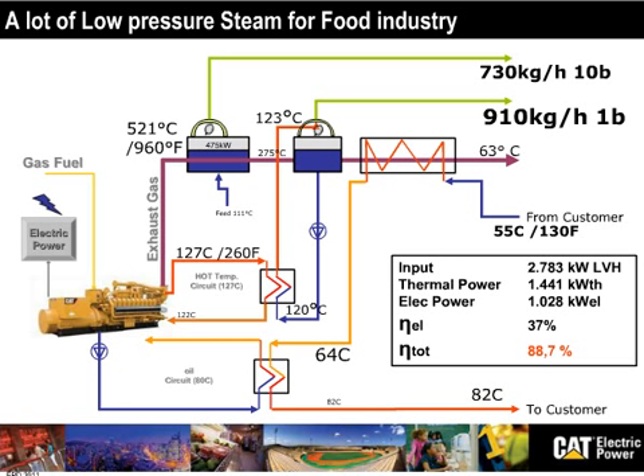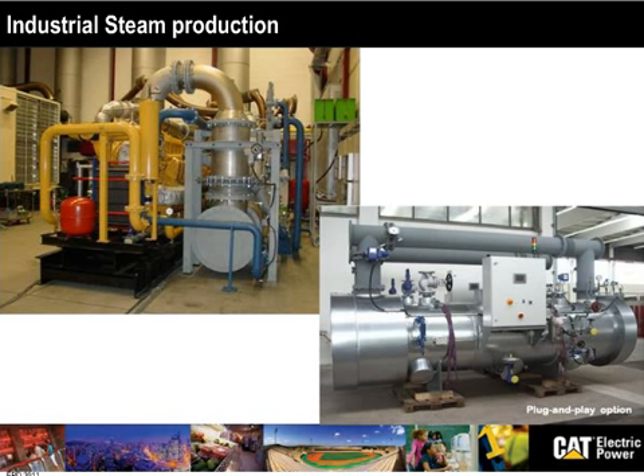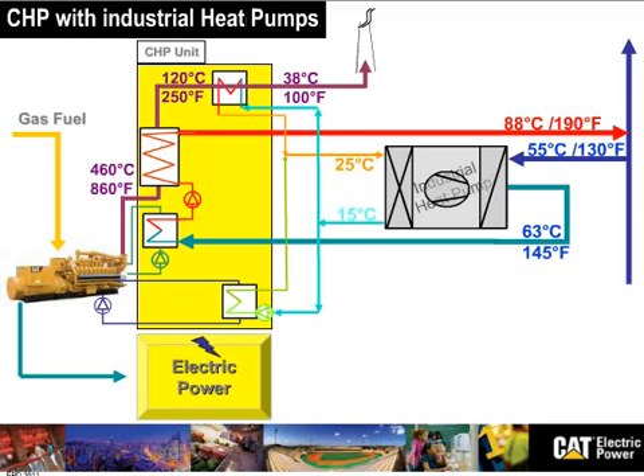Here is an example of how a steam boiler from the waste heat recovery looks like. We normally position it next to the genset. Steam boilers are heavily instrumented, and these are different processes and different equipment than just hot water heat recoveries. So we want heat, and heat is very important, and we have a way to produce more heat. To do that, in a traditional hot water heat recovery, we would incorporate a heat pump. Not a heat pump like the one you may have in your household, but an industrial, high-efficient heat pump. And this heat pump will use the energy that is in temperatures that are normally too low to be recovered.